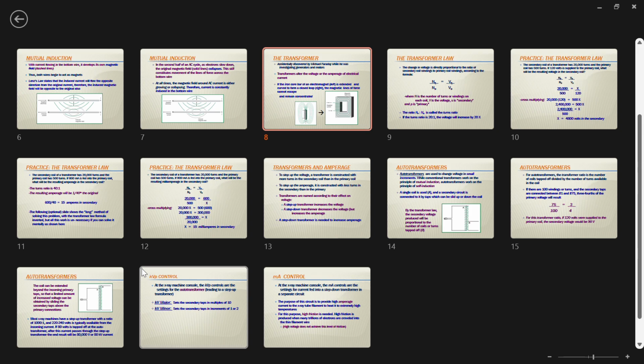So my watts would be 1100 watts. Volts times amps equals watts. So we want to be able to adjust the total power that we're using to create X-rays. We're trying to make an X-ray beam, and each part of the body needs a different amount of power, okay? So we will need to be able to change the voltage and the amperage used, okay?